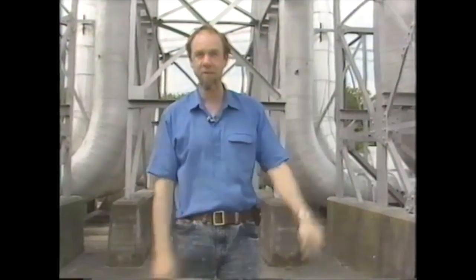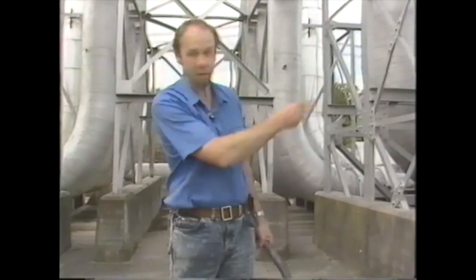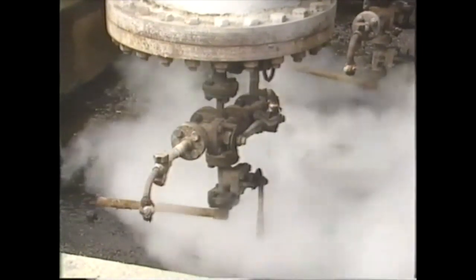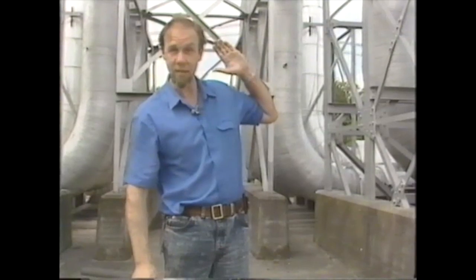And that way, the whole thing remains stable and safe — so one hazard is averted. When the steam gets to the power station, it's got to be absolutely dry, free from any water that would damage the engines. So at the loops and between them, at intervals along the pipe, there are water traps. Water drops into them by gravity and is blown off by steam pressure, and that way the dry steam goes on its way.